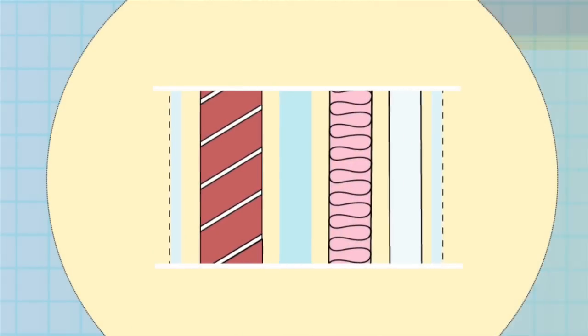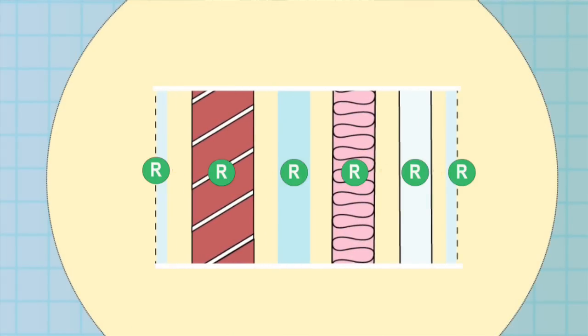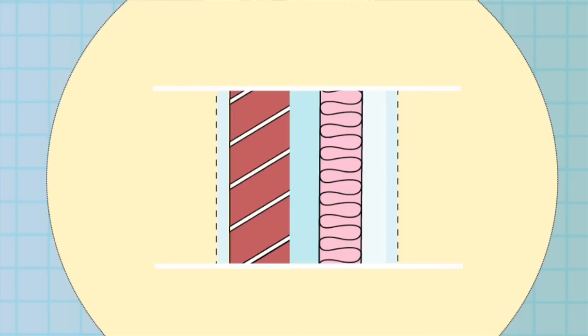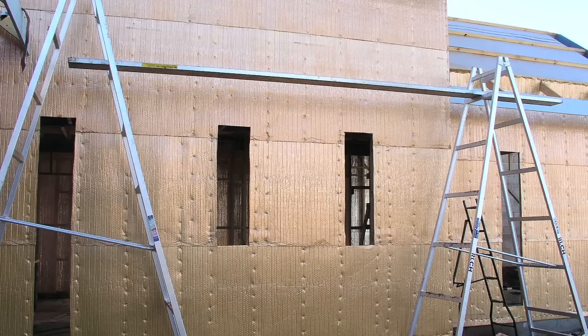The regulations might ask for a system R value or an added R value, so you need to know the difference. The timber, brick, and plasterboard also have an R value, which can be added to the R value of the insulation to give a system R value. The R value of the insulation itself is called the added R value. Only system R values are quoted for reflective insulation, as it depends on how and where it is installed.